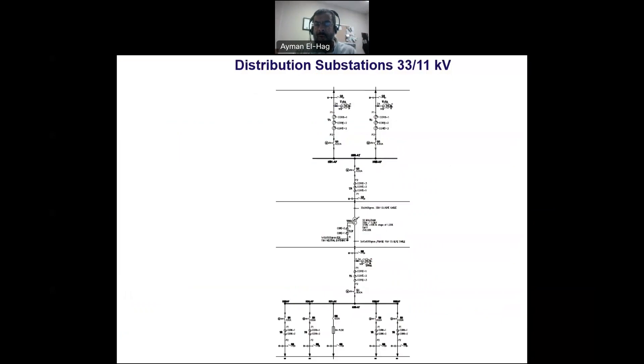Let's move now to the transformer, which is between the 33 and the 11 kilovolt side. This is a 10 MVA transformer. ONAN means oil natural, air natural, meaning that the circulation of the oil inside the tank is done naturally, and the air around the transformer also circulates naturally.